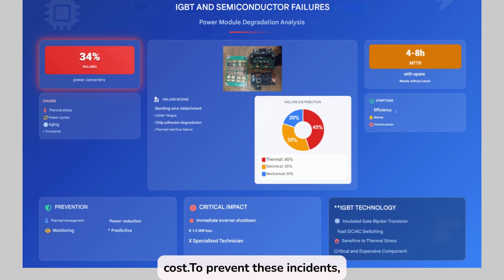To prevent these incidents, the following can be implemented: advanced thermal management, use of active cooling systems, forced ventilation, and high thermal conductivity materials. Thermal sensors distributed across the plate and contact points to detect anomalous heat buildup. Predictive monitoring based on artificial intelligence. Detection of thermal and electrical drift before failure occurs. Scheduled power reduction. Mitigation strategy in times of extreme risk, for example, prolonged heat waves, dirt buildup, severe weather events.